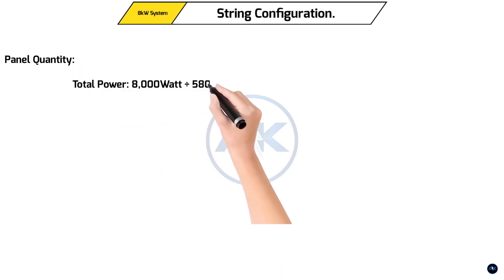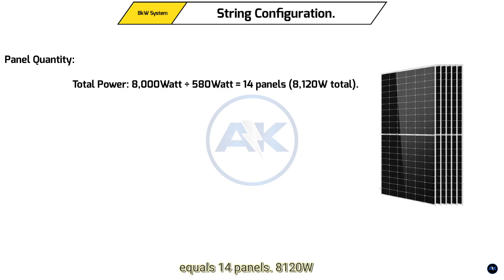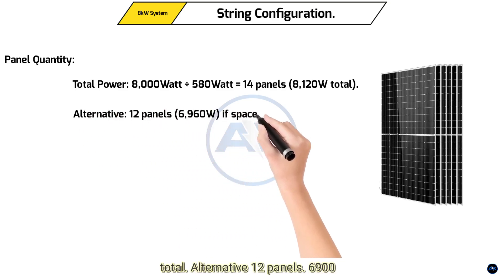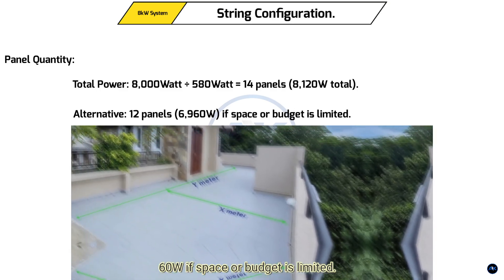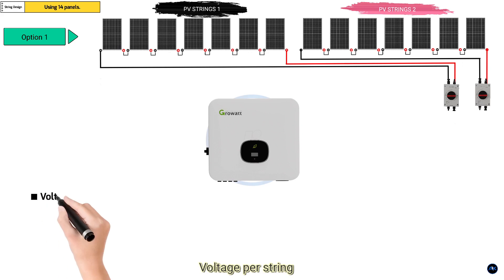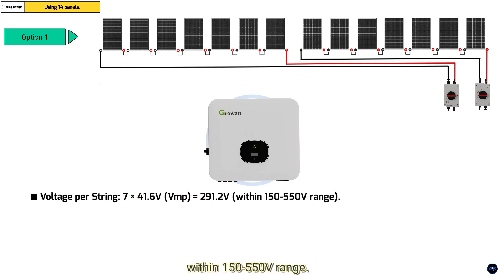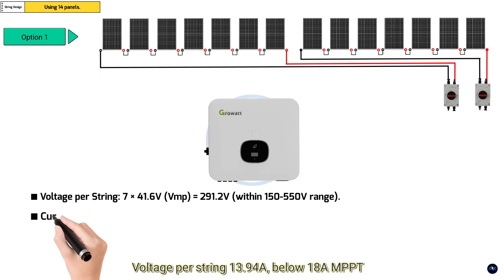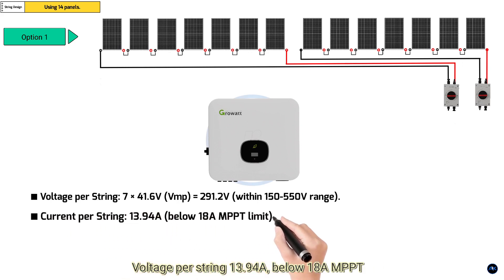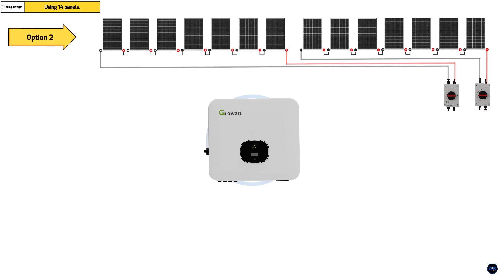String configuration for the 8 kilowatt system. Panel quantity: total power 8,000 watts divided by 580 watts equals 13.8 — so 14 panels at 8,120 watts total. Alternative: 12 panels at 6,960 watts if space or budget is limited. String design using 14 panels — Option One: two strings of seven panels each, best for the Growatt's MPPT range. Voltage per string: 7 multiplied by 41.6 volts Vmp equals 291.2 volts — within the 150 to 550 volt range. Current per string: 13.94 amps, below the 18 amp MPPT limit. Total power: 8,120 watts, within the 10.5 kilowatt inverter limit.